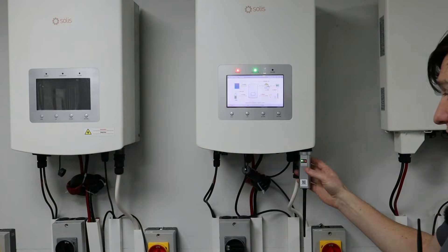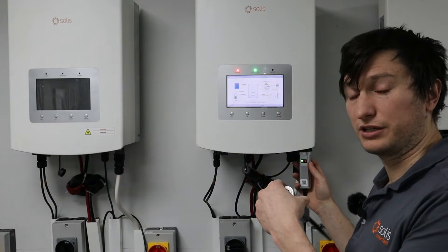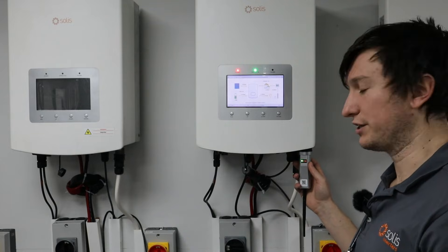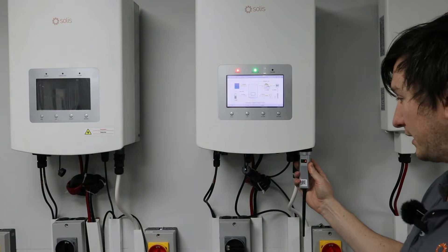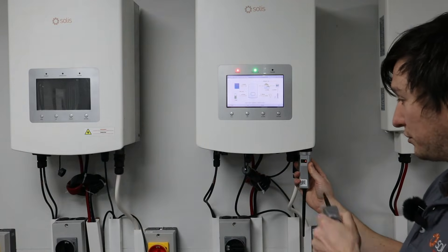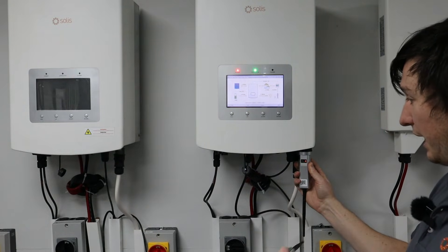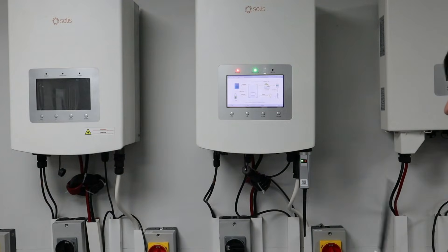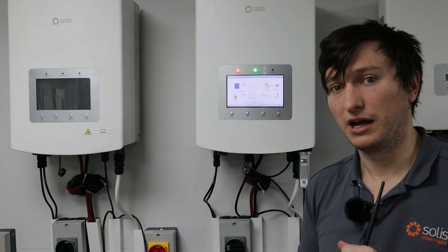If you ever want to reset the data logger, press and hold the button at the back for 10 seconds. It goes into a first state of blinking quickly, which is configuration mode, then it goes completely blank — that means it's in reset mode. It should now not connect to the Wi-Fi network in the building and should remain offline and not communicating to SolisCloud.